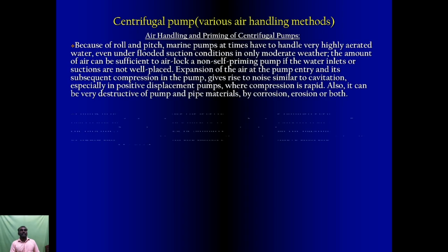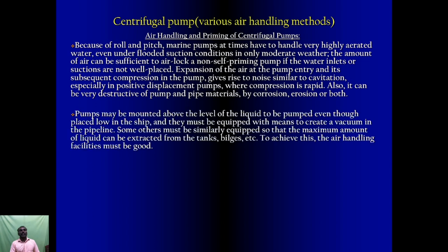Because of the roll and pitch, marine pumps at times have to handle very highly aerated water, even under flooded suction conditions in only moderate weather. The amount of air can be sufficient for an air lock in a non-self-priming pump if the water inlets or suctions are not well placed. Expansion of the air at the pump entry and subsequent compression in the pump gives rise to a noise similar to cavitation, especially in positive displacement pumps where compression is rapid. Also, it can be very destructive of pump and pipe material by corrosion, erosion or both.